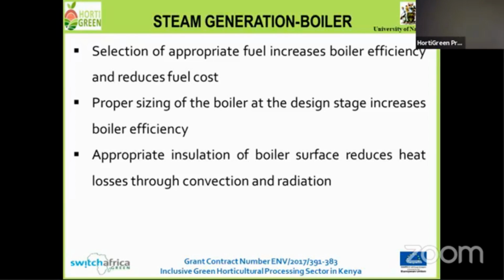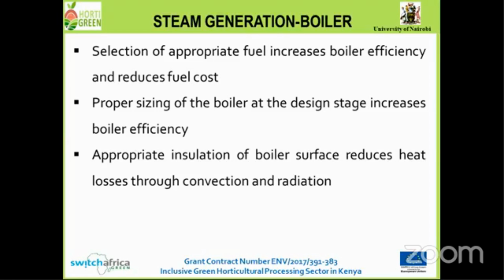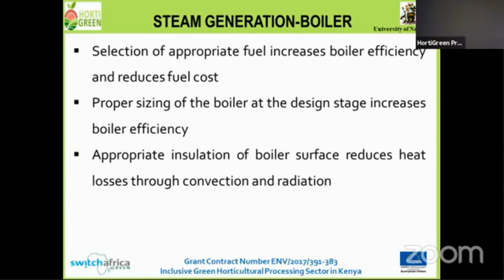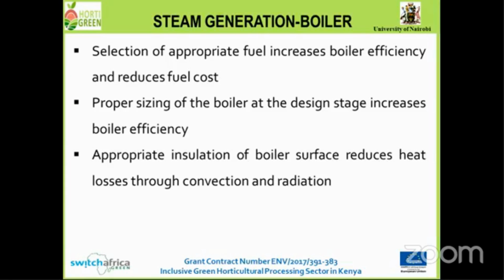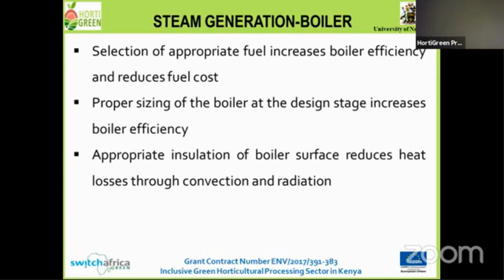And the boilers use, of course, the various types of fuel that are mentioned to generate steam. And selection of appropriate fuel increases boiler efficiency and reduces fuel cost, where efficiency here refers to the percentage of the thermal energy in the fuel that ends up in the steam that is generated. And proper sizing of the boiler at the design stage, or indeed at the time of purchase of the boiler, is important because if it is too big, then capacity utilization will be low and efficiency will be reduced.